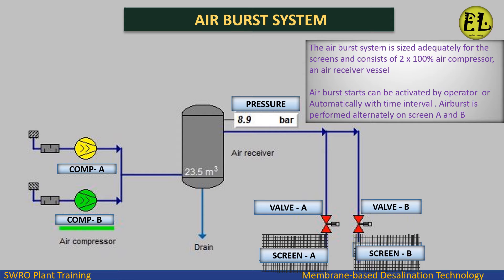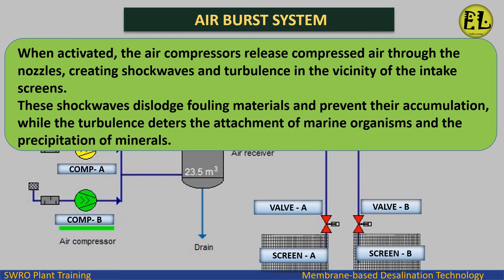Airburst starts can be activated by an operator or automatically at a set time interval. Airburst is performed alternately on screen A and B. When activated, the air compressors release compressed air through the nozzles, creating shockwaves and turbulence in the vicinity of the intake screens. These shockwaves dislodge fouling materials and prevent their accumulation, while the turbulence deters the attachment of marine organisms and the precipitation of minerals.